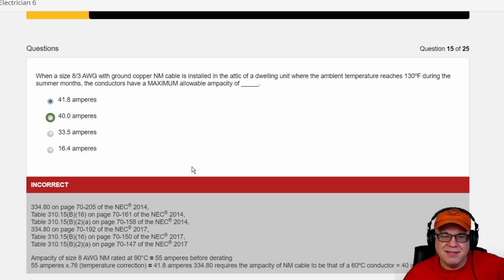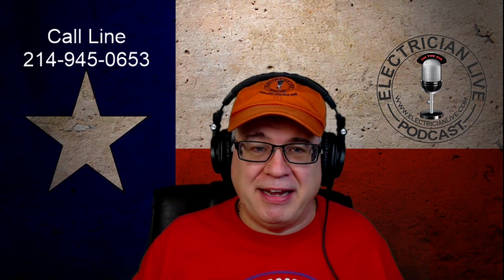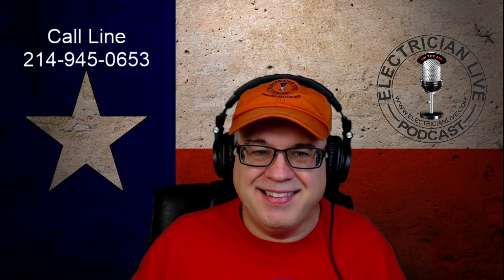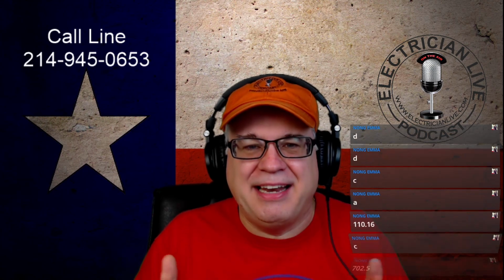Why is it 40? I'll let somebody tell me. There's a reason why I just went through all that. Remember I said it's still 40? I'm sorry, I had to do it that way. But there's a reason why. So it still has an ampacity. Wait a minute. I think Danny got it. Yeah. Excellent. Even after all of that, you're still limited to the 60-degree column. All you were doing is making sure that your conductor still could carry what was under the 60-degree column, because you're limited to 60 degree for NM-B.